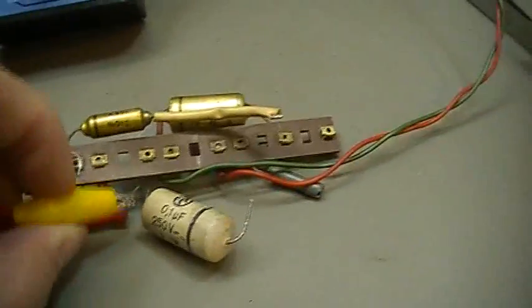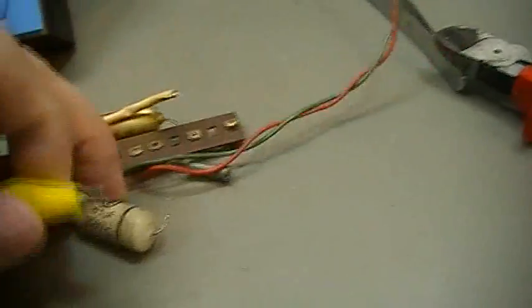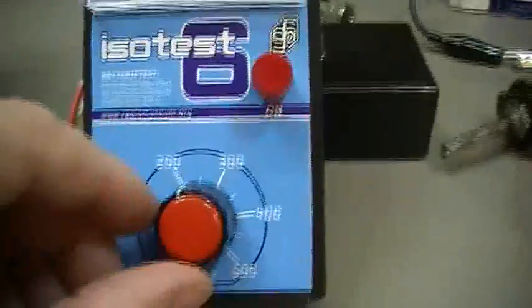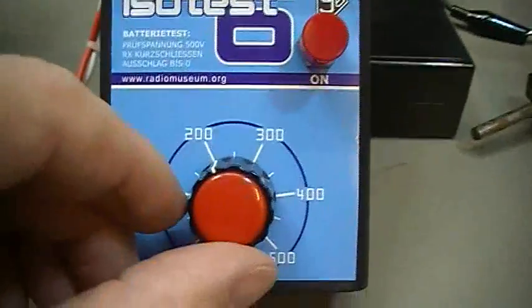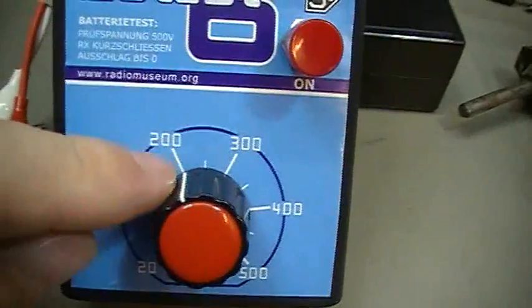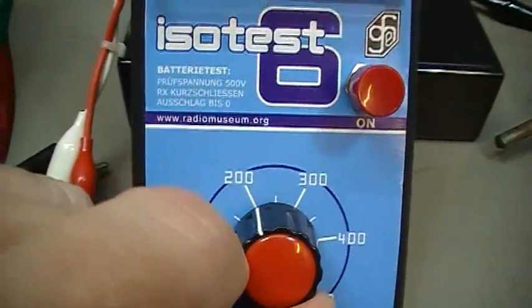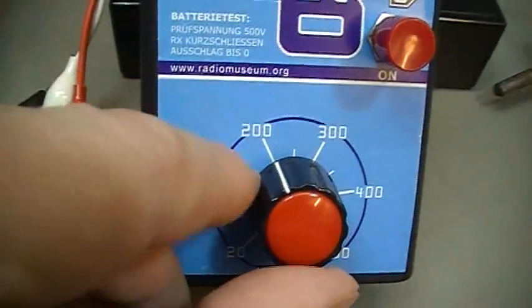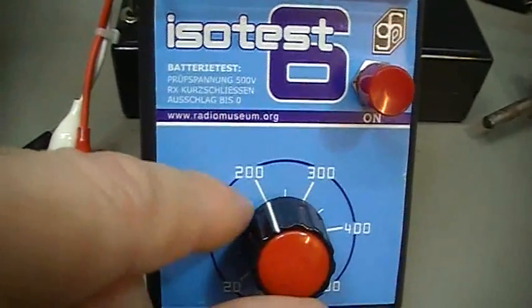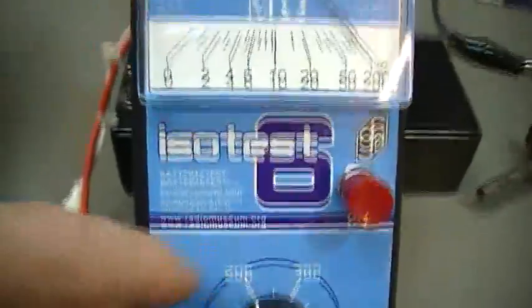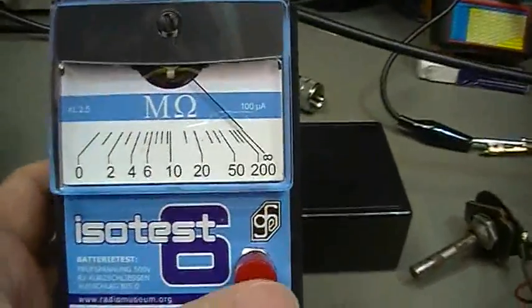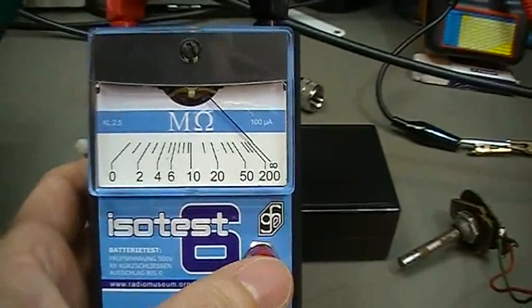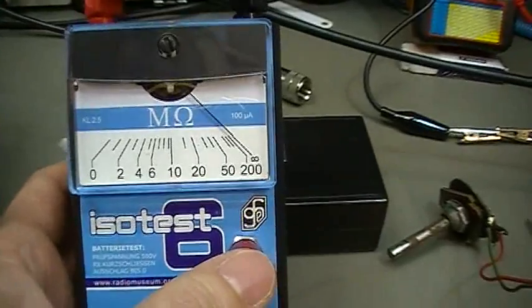If we now connect the leads to our capacitor, so now it is connected, and my isolation tester is adjusted. You may see the white line here, the indication where I have put it on the scale, and it is now adjusted to 200 volt DC. Now I press the test button, and yeah, we can see both. You should watch the needle for movement.